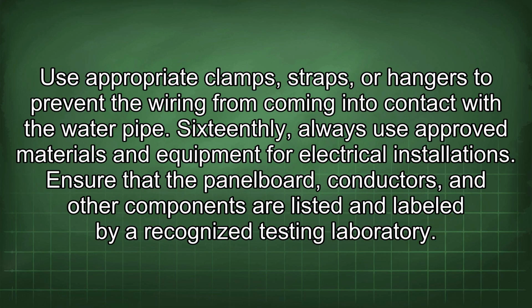Use appropriate clamps, straps, or hangers to prevent the wiring from coming into contact with the water pipe. 16thly, always use approved materials and equipment for electrical installations. Ensure that the panel board, conductors, and other components are listed and labeled by a recognized testing laboratory.